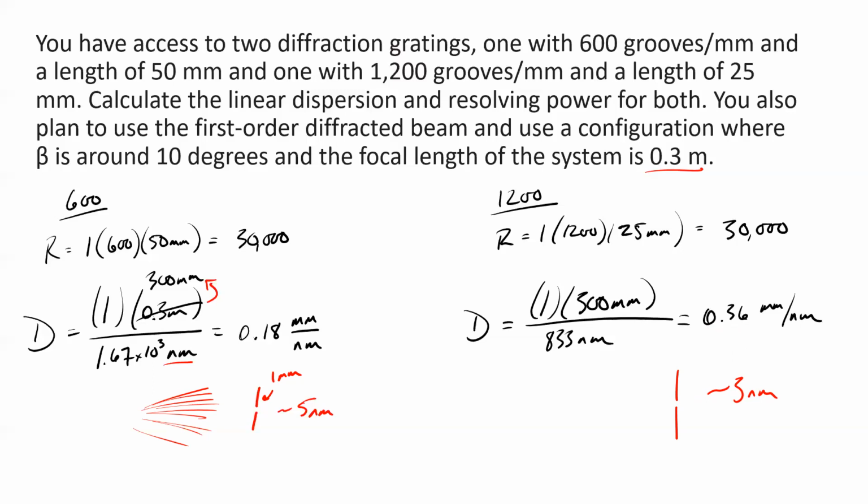Are you following? Does that make sense? Yes, no, maybe? So, are you saying that you want less to get through? Yes. If I'm only interested in seeing how much my molecule absorbs at 505 nanometers, then I really only want to look at 505 nanometers, not 506 and 507 and 508 and 509 and 510. I only want 505. And so it is a good thing to have less light coming out of the instrument, a narrower range of light coming out of the instrument.